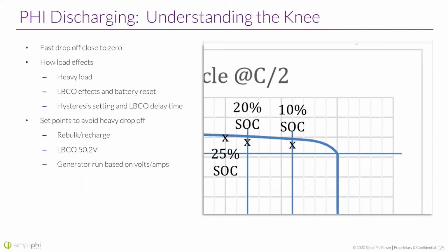So load affects this. A C/2 load is going to make this more drastic and make the battery voltage drop very quickly if you have a heavier load on the battery than a typical residential load. Now, low battery cutout is a function in an inverter that can put the inverter into standby so that you do not have to manually reset the system or the batteries. With this knee, and a heavy load on the system, you could possibly trigger the low battery cutout in the battery before you trigger it in the inverter. This would cause the installer to have to go out and manually reset the batteries. So we want to try to avoid that.